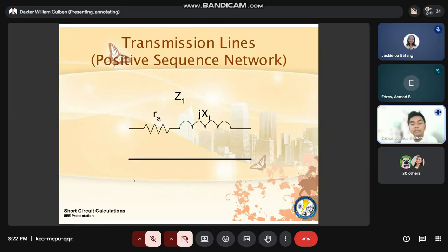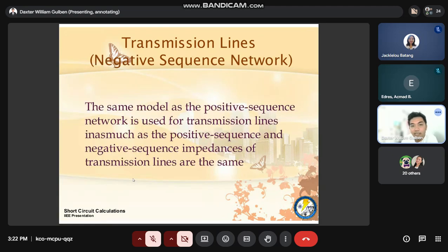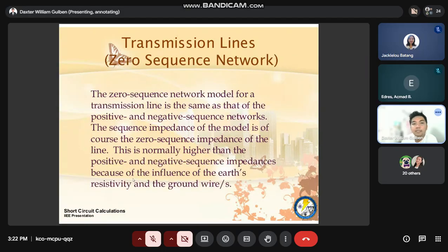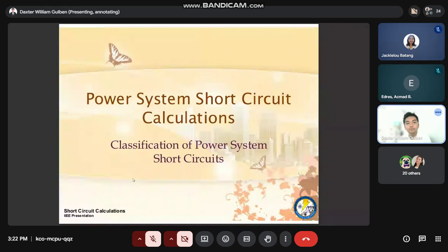Okay, let's move on then. Now, in transmission lines, a typical Z1 is just your equivalent line impedance based on our midterm computations. This is the calculation of the impedance. And negative sequence is the same as your positive sequence for transmission lines. And your zero sequence for transmission line is the same as that of the positive and negative sequence.